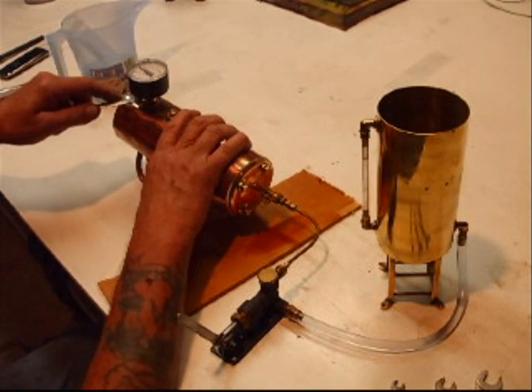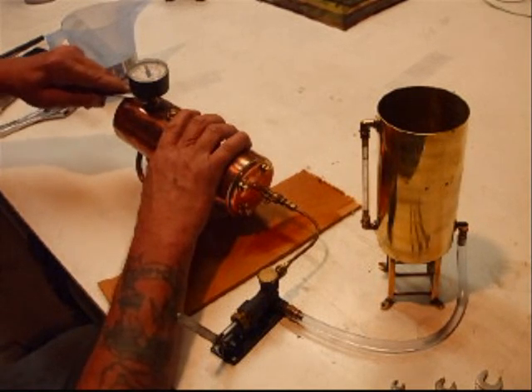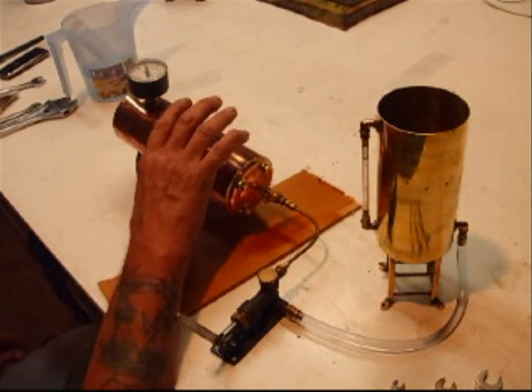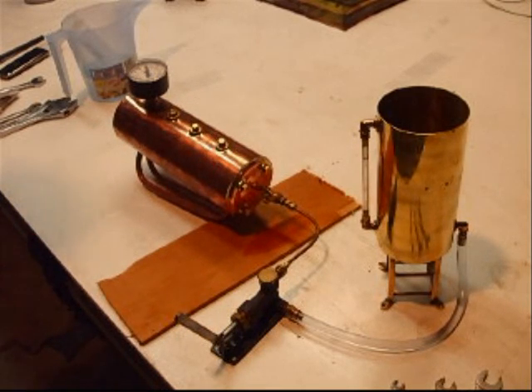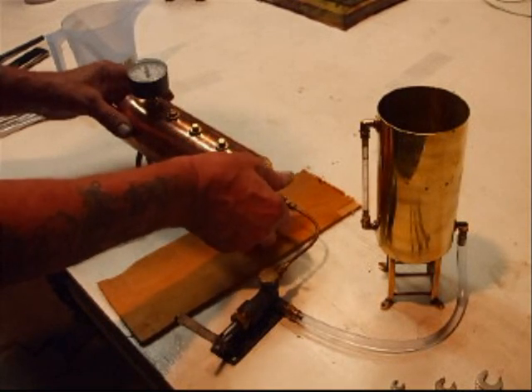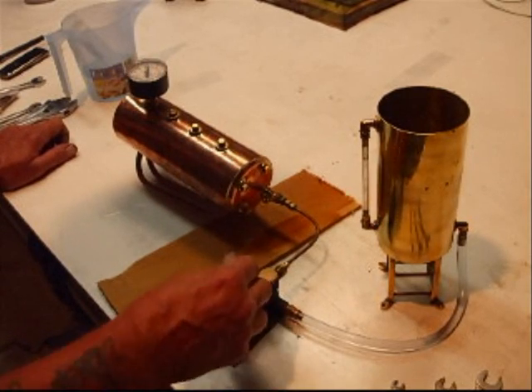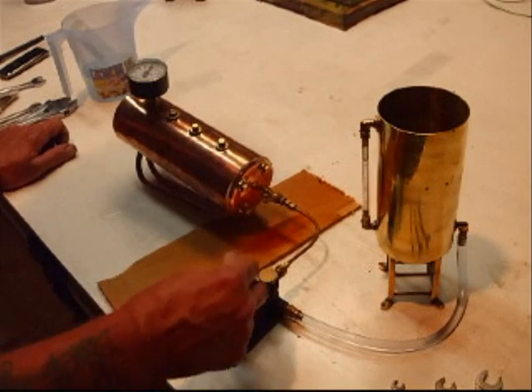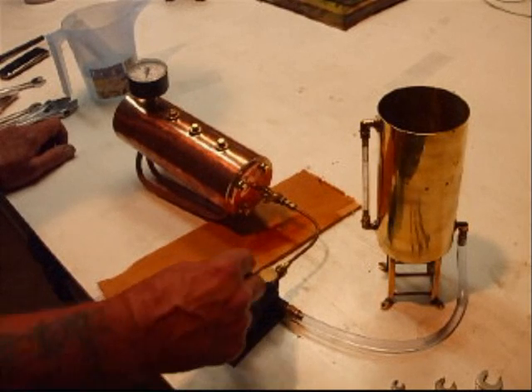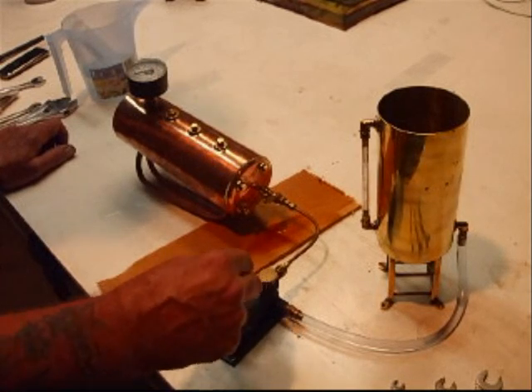Which is a 5/16 inch fitting on the boiler. Let's pump and see what happens. The gauge is coming up: 40, 50, 60, 70, 80, 100, 120, 150 psi.